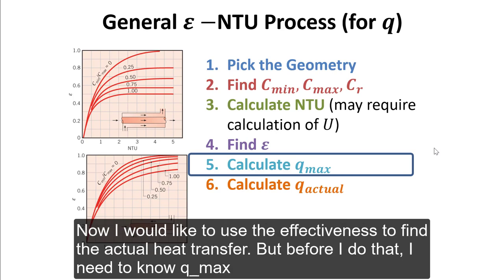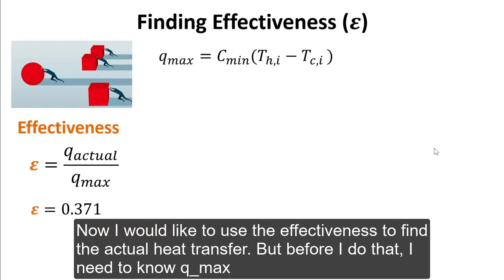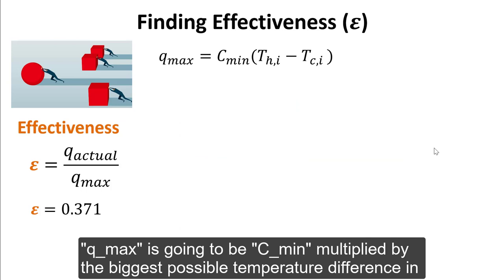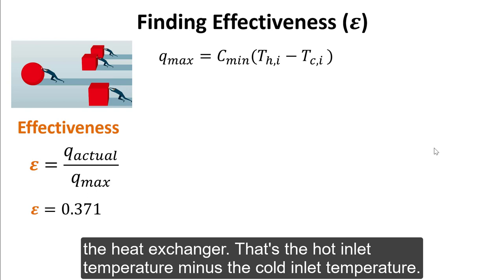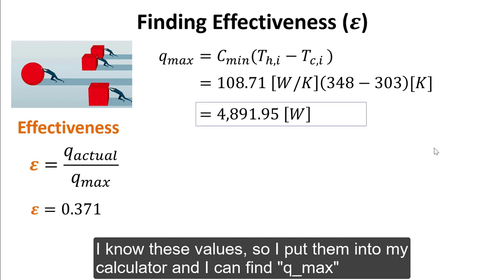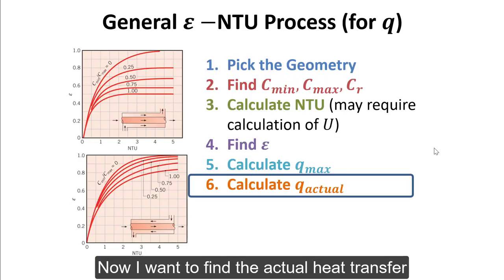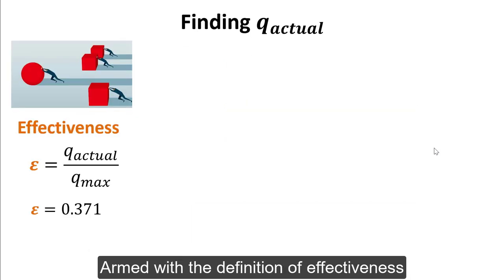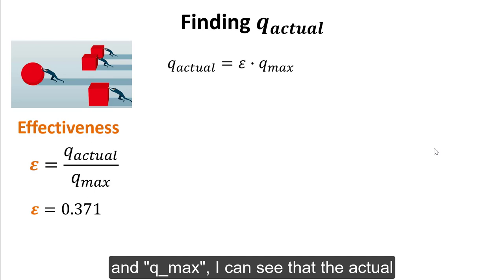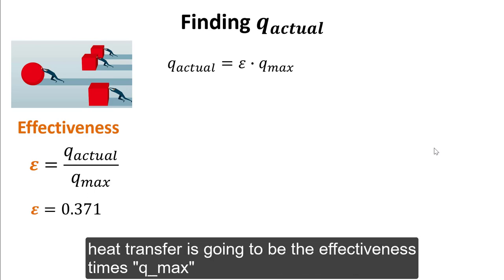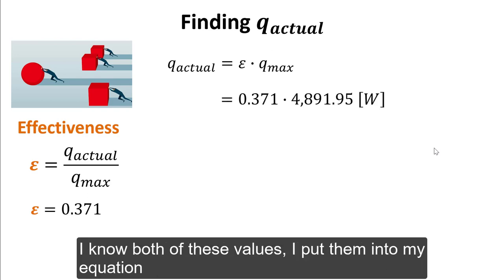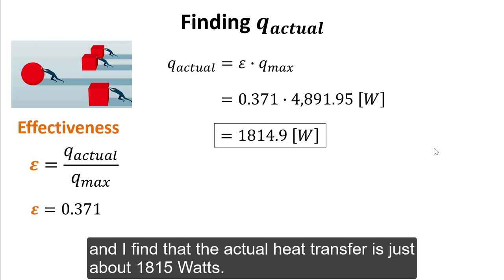Now I'd like to use the effectiveness to find the actual heat transfer, but first I need to know Q max. Q max is C min multiplied by the biggest possible temperature difference in the heat exchanger — that's the hot inlet temperature minus the cold inlet temperature. I know these values, so I put them into my calculator and find Q max. Then the actual heat transfer is the effectiveness times Q max, and I find that the actual heat transfer is just about 1,815 watts.